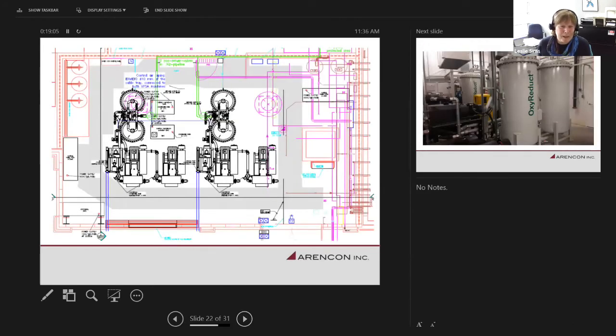This is a drawing from one of the plants and one of the facilities. You'll have the compressors lined up, and then you'll see the two circles are the nitrogen generator or nitrogen filters. You have two because one is doing the separation of the nitrogen, loaded with the pressure, and the other one is returning to ambient pressure and releasing the oxygen. So they cycle on and off. In this case, we had two systems, and each system technically could feed the building sufficiently, but it would be running a lot. So there was another level of redundancy.